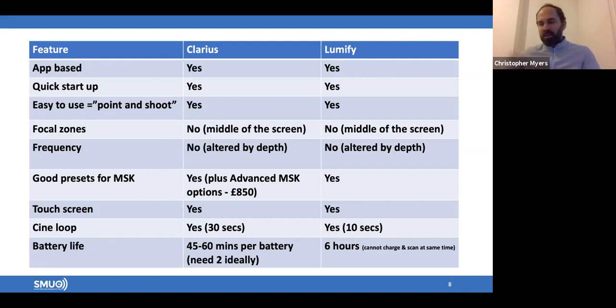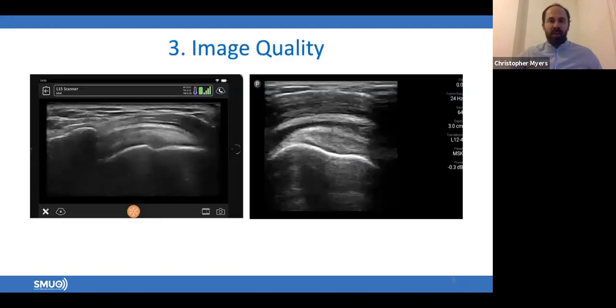The important thing is not to put it down and forget about it, because that battery is still being used. And then you pick it back up and it will be dead, the battery. So you need to make sure that when we talk about 45 to 60 minutes, we mean continuous scanning. So as long as you remember to switch it off into power save mode between, then you're not going to have so much of a problem with that.